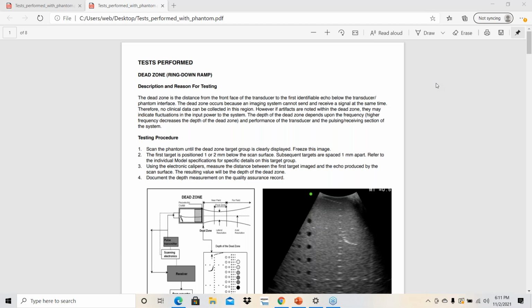And you want to know what dead zone you have to begin with, because if there's degradation on the system over time, you want to know that that's happening. So if your dead zone goes from, you can see this dot, and then the next time you test it, you can only see this one. Well, clearly something's changed on your ultrasound, so you want to measure that dead zone and have just a measurement in your records, so over time you can see if the dead zone's changing. Now it'll be different per probe. So you want to do this test on every probe. The higher the frequency, the closer the dead zone should be to the top. So you should have a smaller dead zone, right? The higher the frequency.